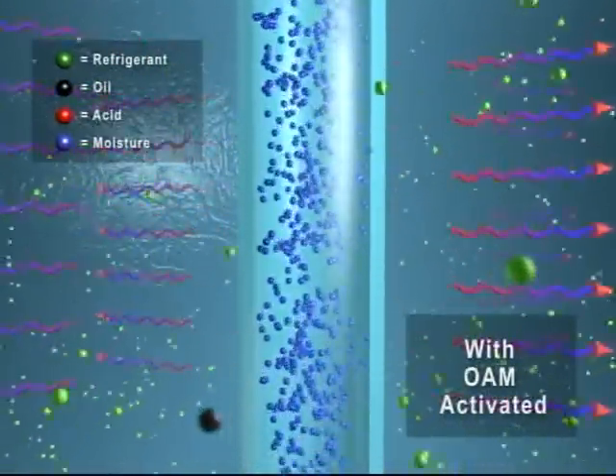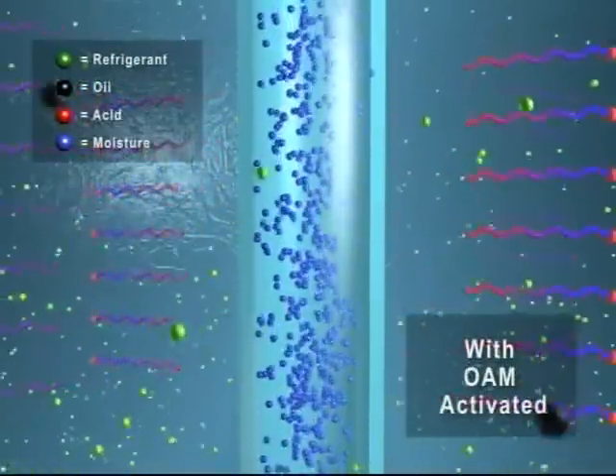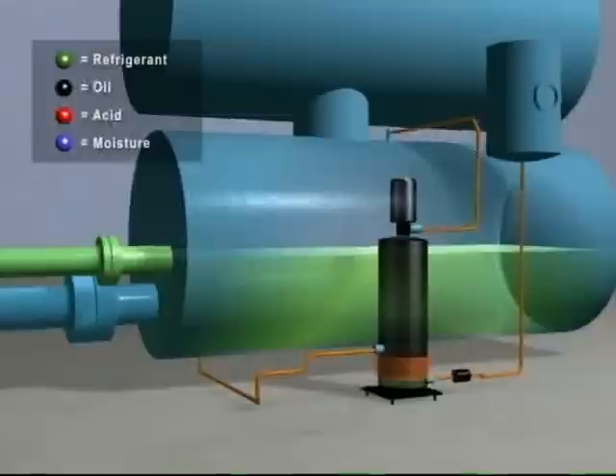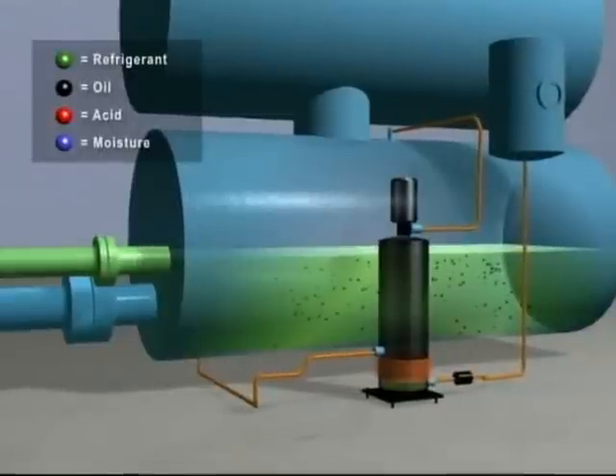Even at 1% to 2% oil by weight, the heat transfer coefficient is reduced by 1/3 from its no oil baseline. At a substantial oil content of 5% to 15%, a 40% to 50% reduction is noted. Part 2 of this study obtained a similar conclusion.